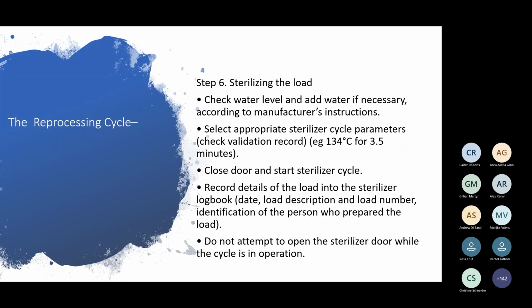So, sterilizing the load, always check your water levels. If you don't have a machine that is auto-filling, make sure you check your water levels and add water prior to commencing the load, because if you don't have enough water in it, the machine may fault and stop halfway through the cycle. Select your appropriate sterilizer process, so 134 at 3.5 minutes, close your door and start your sterilizer cycle. Put your records of the load into the sterilizer logbook: your date, load description, load number, identification of the person who prepared the load. And don't attempt to open the sterilizer door while the cycle is in operation.